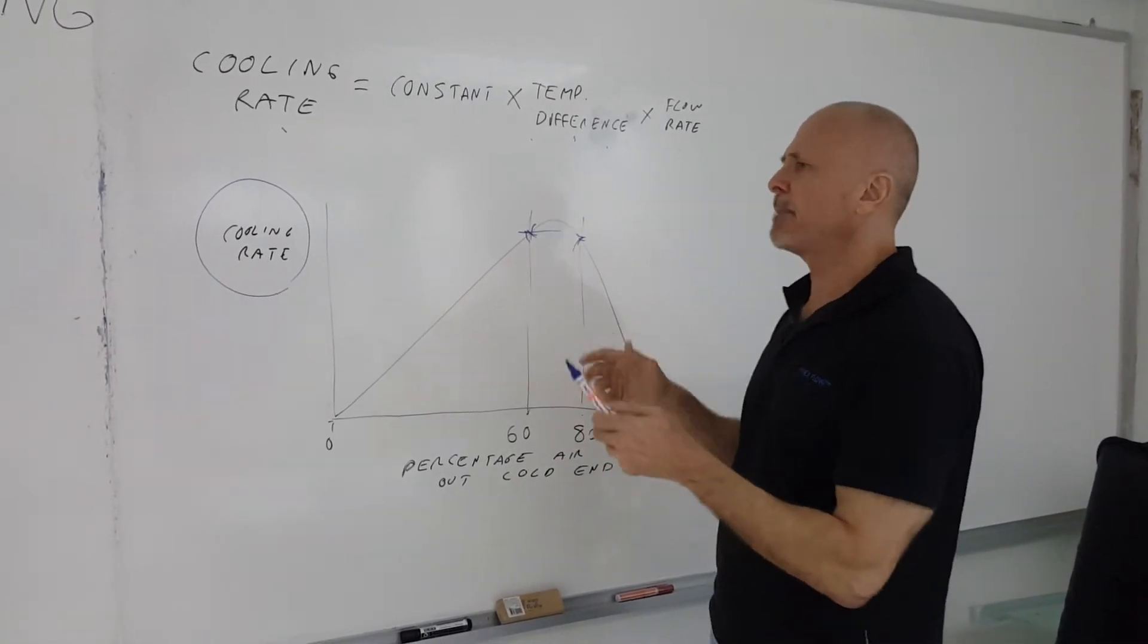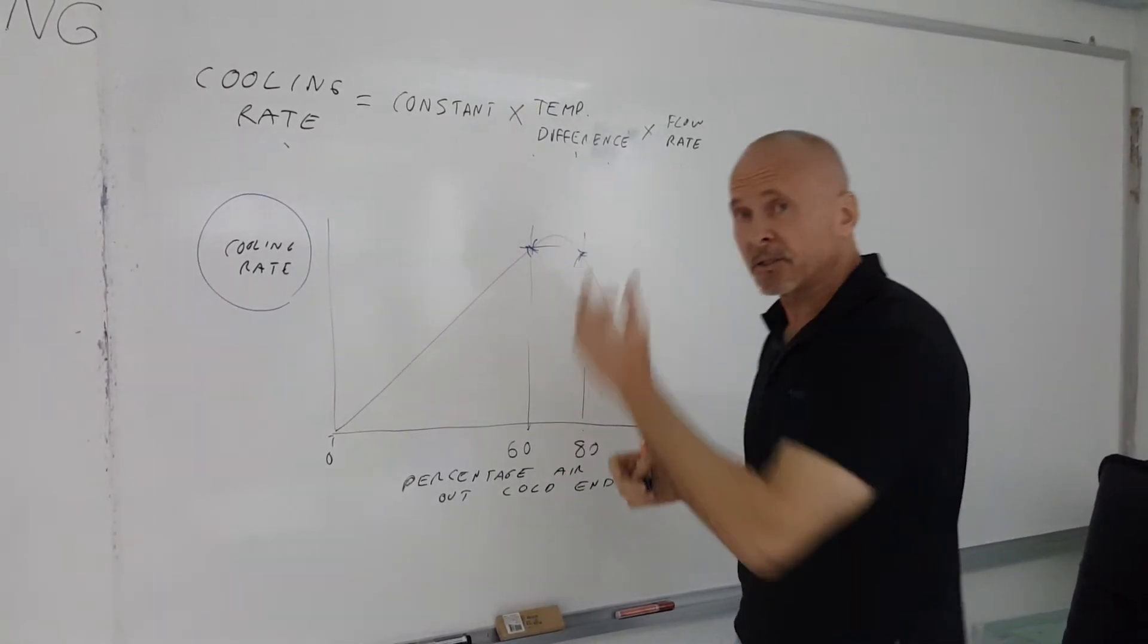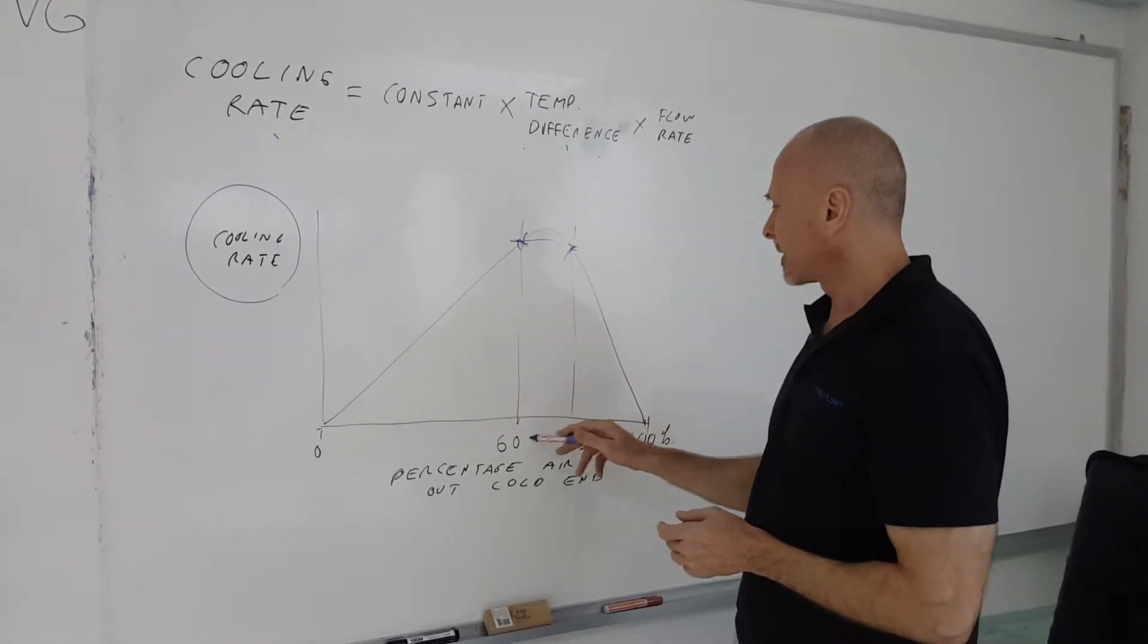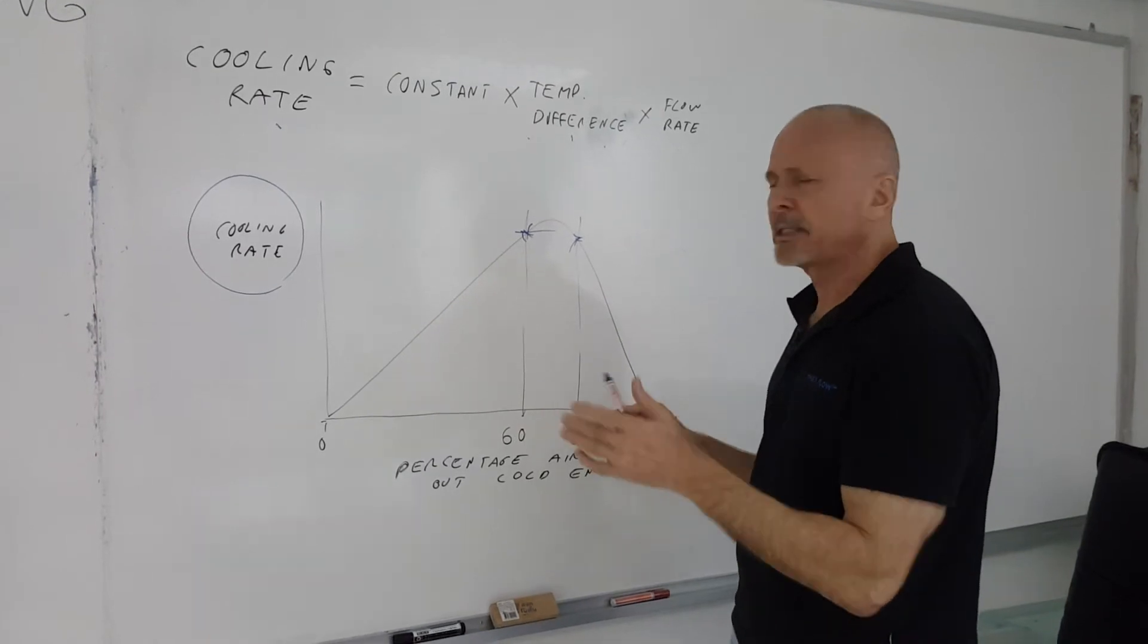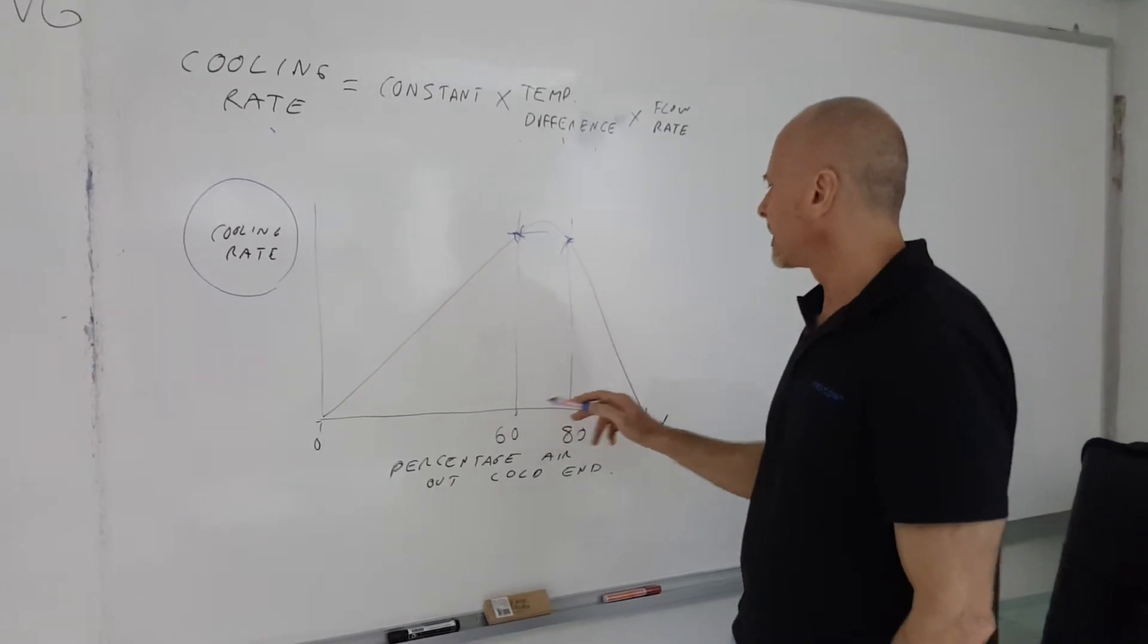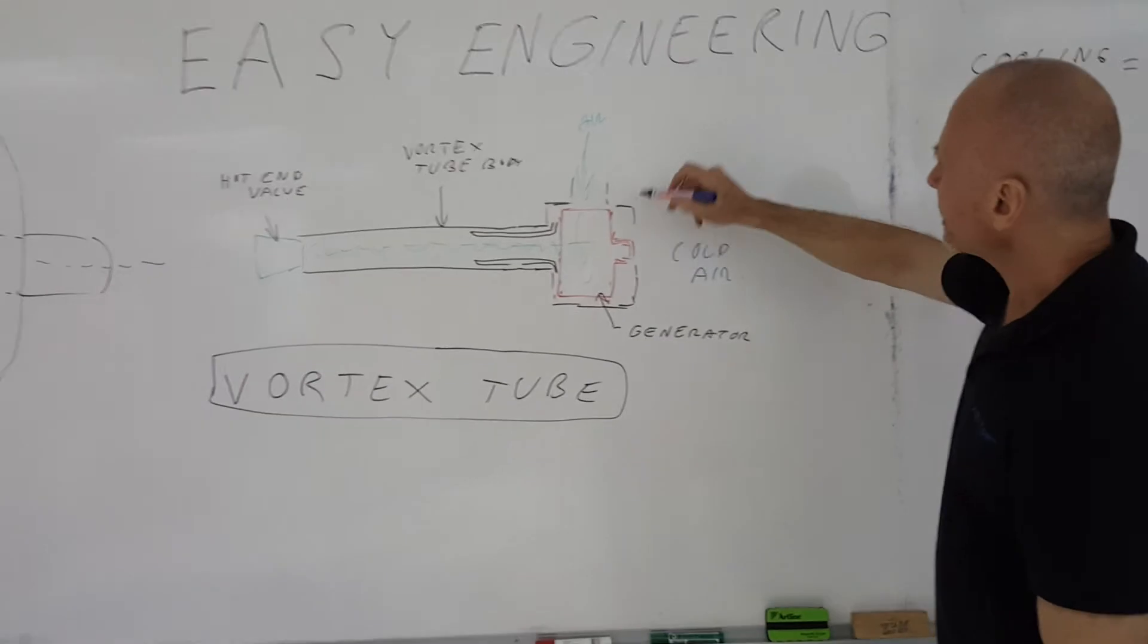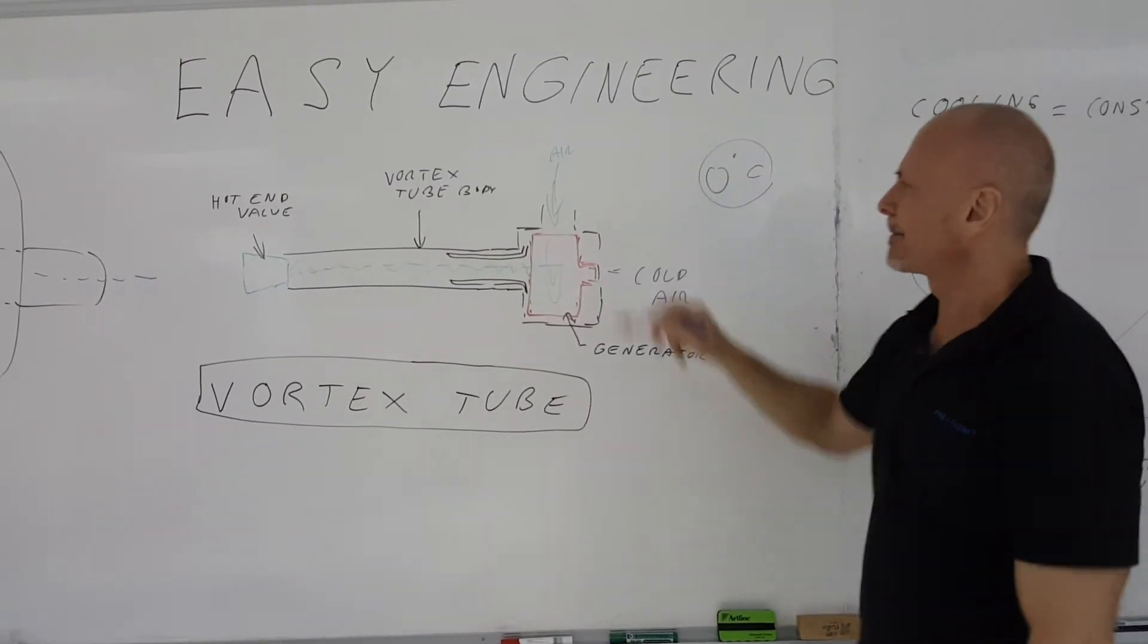And then the same thing with the temperature of the compressed air going into the vortex tube. The temperature of the compressed air going into the vortex tube is higher, you're better off at the 60 than the 80. So somewhere between 60 and 80 seems to be an optimum level. What's interesting is that if you have the compressor operating between 60 and 80% going out the cold end, you actually get a temperature somewhere around zero degrees Celsius coming out of the cold end.